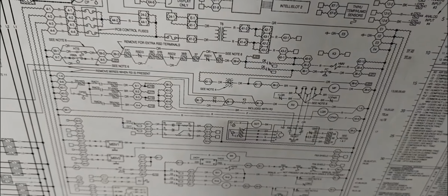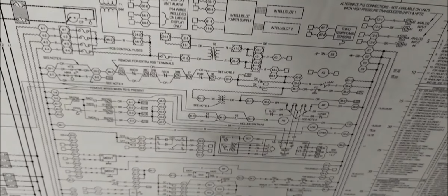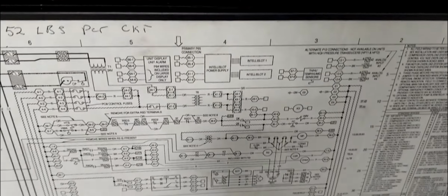So now I'm going to open up this unit and I'm going to go in and I'm going to check on the main fan. There should be something there that's going to show me an overload that's going to be open. So stay tuned. Next phase of the troubleshooting. So to access the main fan, you're going to have to open these right here in the bottom. So I got to open these with my Allen key.